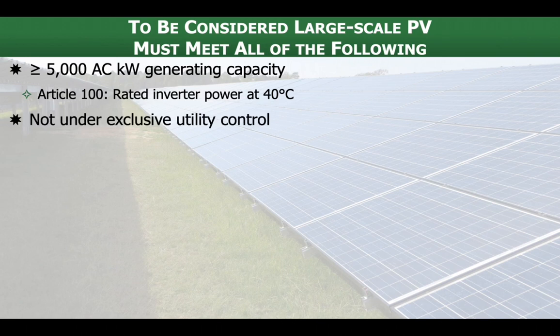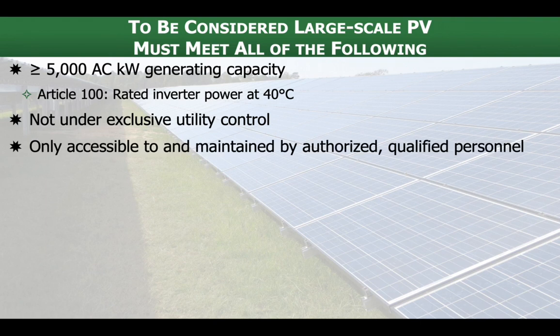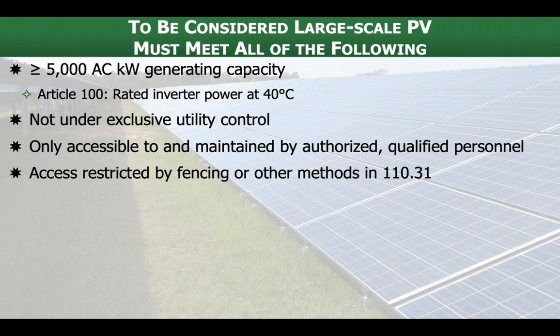The system is not under the exclusive control of the utility. They may have operational input in terms of SCADA systems that can control what's going on with the system, but they do not own it and perform the operations and maintenance, even if they do have that capability. They are not the exclusive operators of it. The system is only accessible to and maintained by authorized qualified personnel. Part of that is having a way to restrict access. Usually that's by a fence. So we're only letting in people that know what they're doing and know how to do it safely. They're performing work on a power plant, essentially.